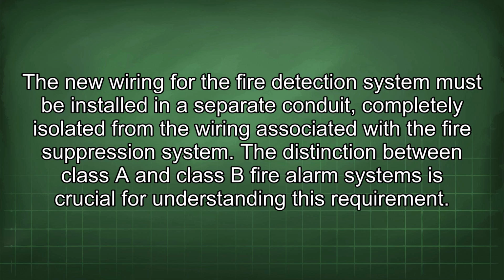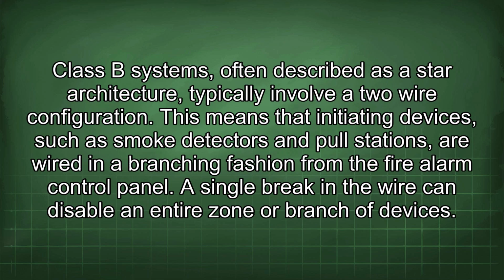The distinction between Class A and Class B fire alarm systems is crucial for understanding this requirement. Class B systems, often described as a star architecture, typically involve a two-wire configuration. This means that initiating devices such as smoke detectors and pull stations are wired in a branching fashion from the fire alarm control panel. A single break in the wire can disable an entire zone or branch of devices.